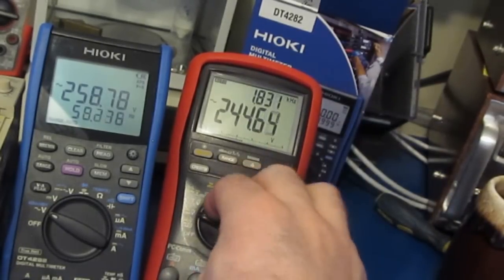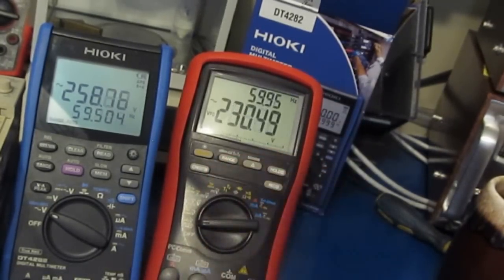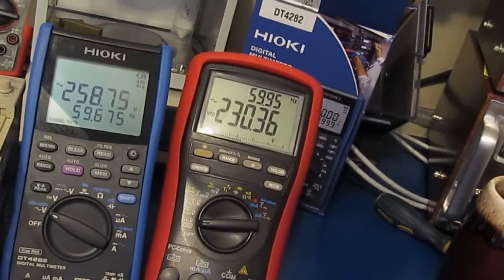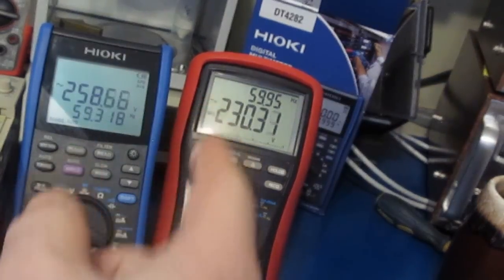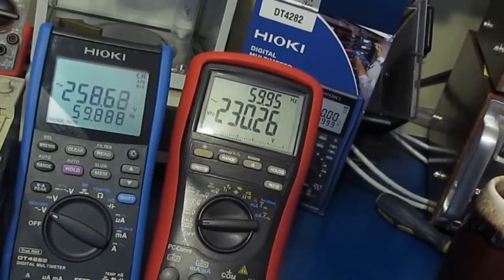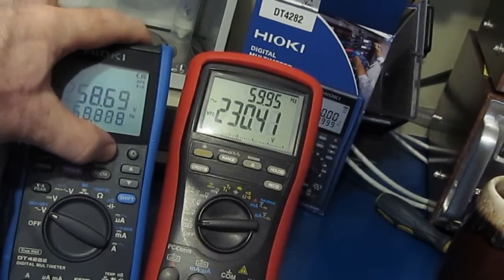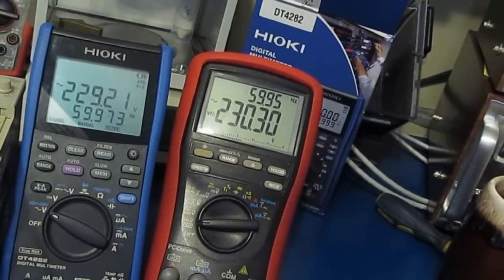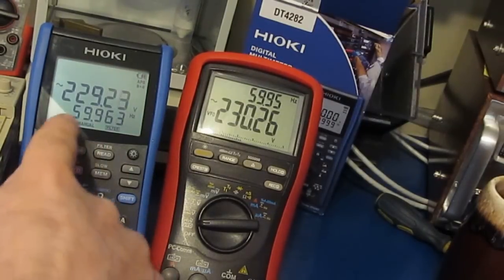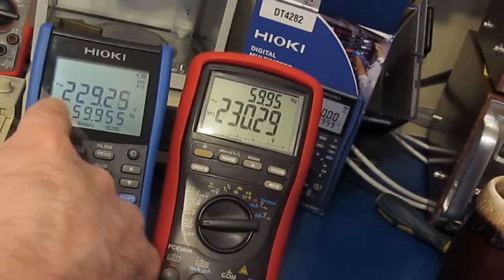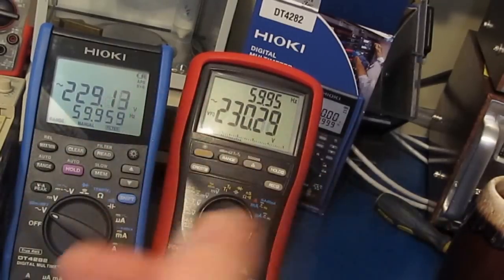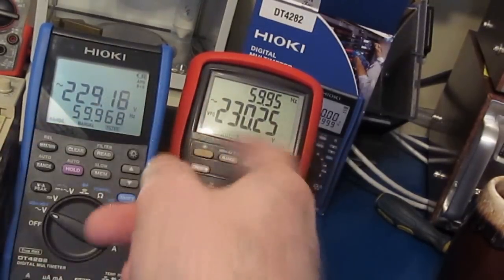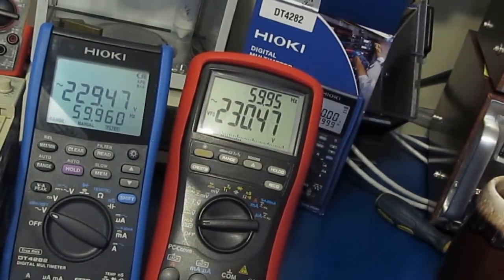What I'm going to do is just select the VFD mode on the Brymen, try to filter that down, and you can see now it's reading 60 hertz and about 230 volts. This is probably correct. Now with the Hioki, they have a filter feature - let's go ahead and enable that. You can see it's now displaying 60 Hertz at 229.3 volts. So the two meters are now basically matching.